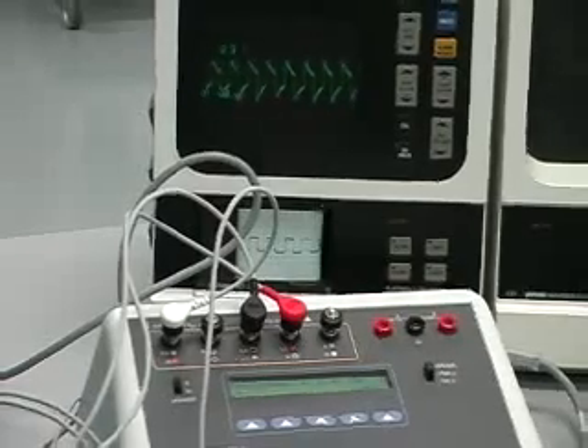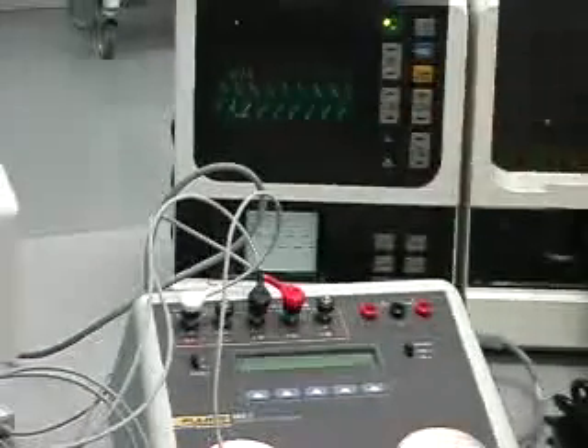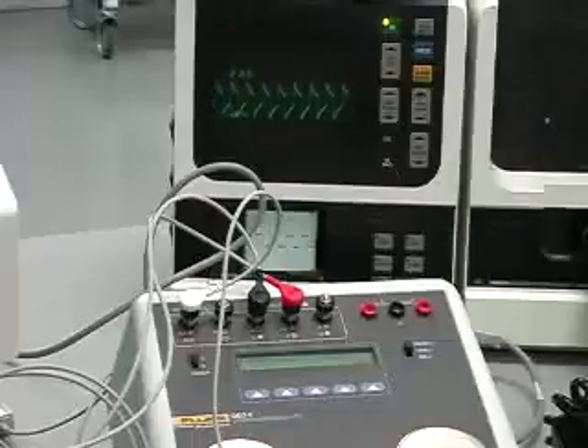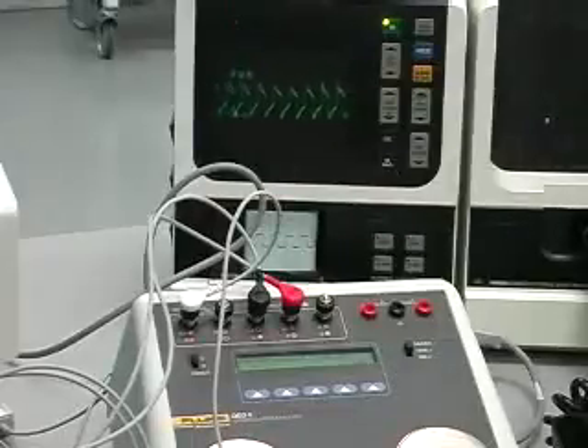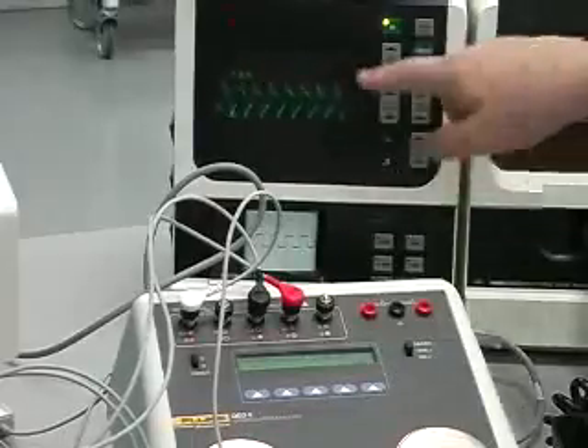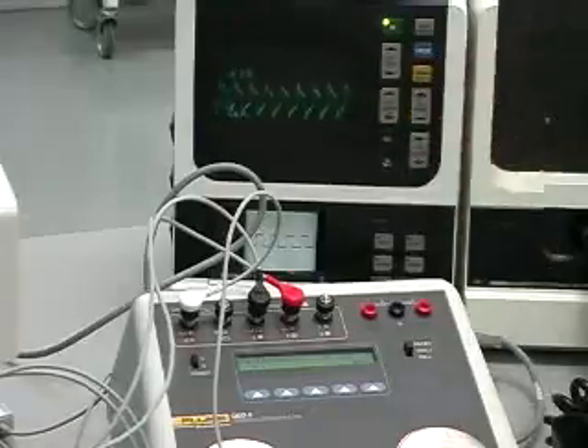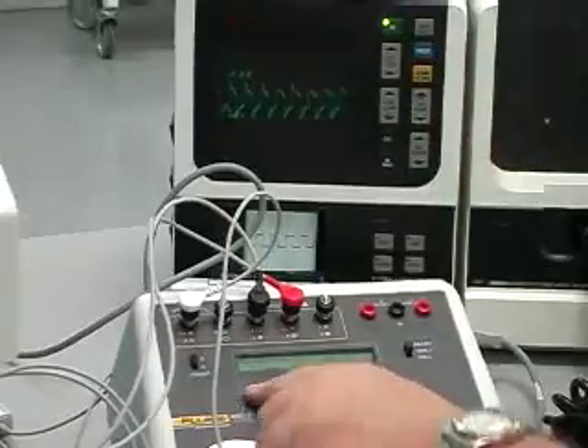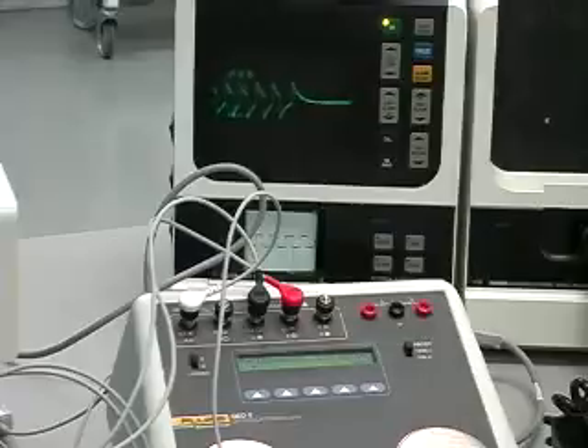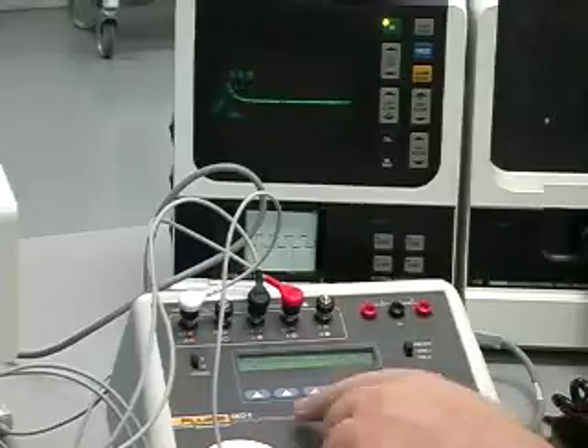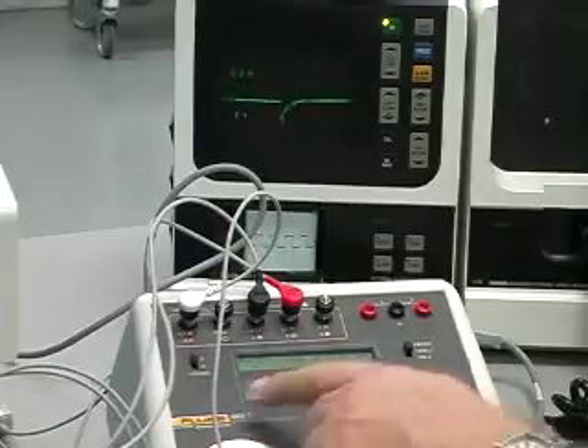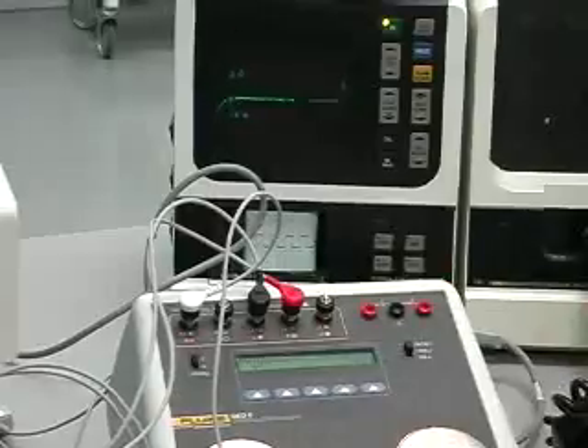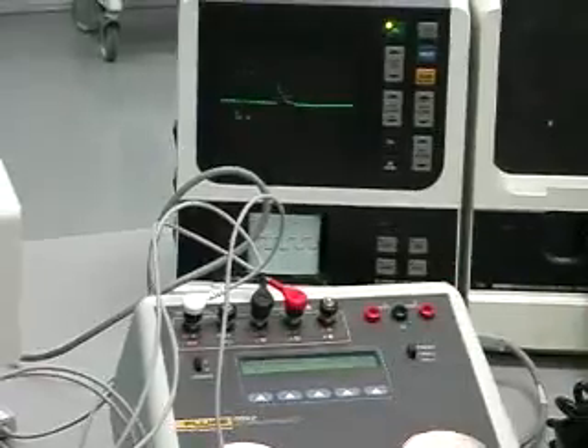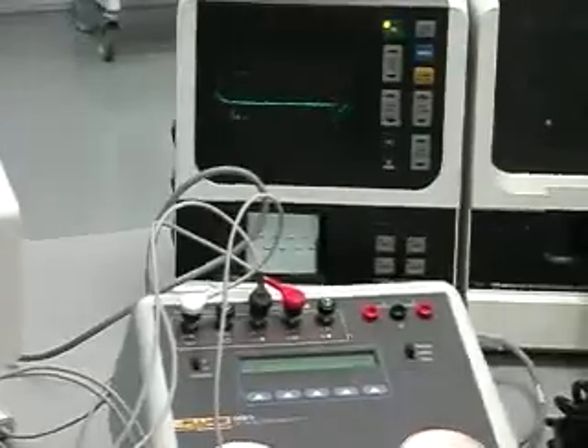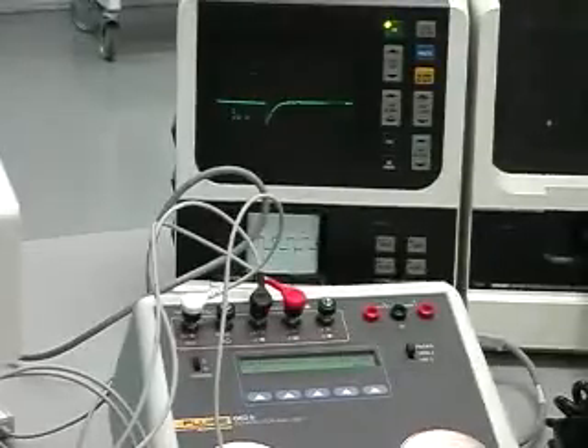And again, the low-end frequency response of the monitor by design doesn't go down that low, so you will have that fast discharge decay of the square wave. Go again to different waveforms for checking low-end frequency response. You're looking at basically over a 4-second DC pulse, and you're just looking to see how long the system will hold a DC or low frequency value.